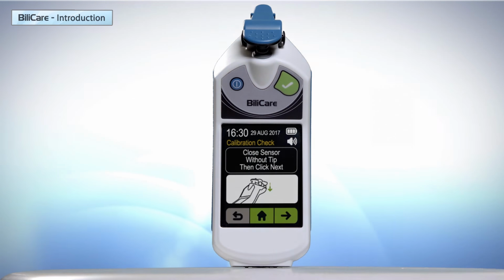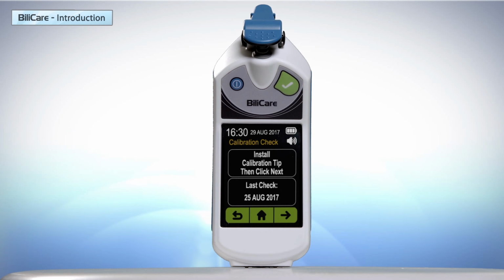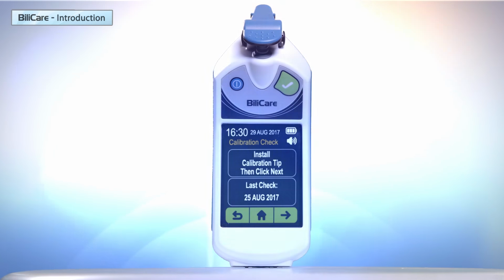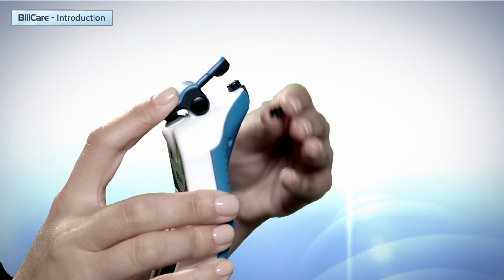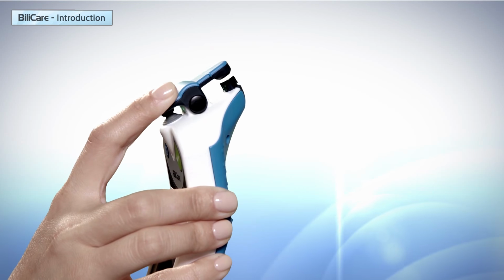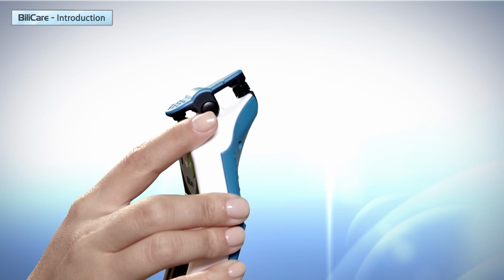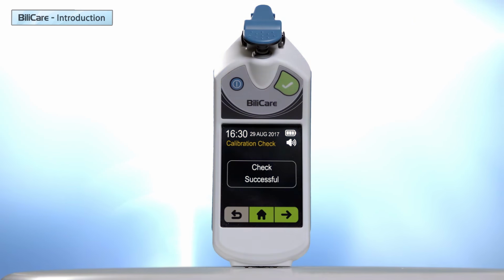Click Next. The next screen asks the user to place the calibration check tip. Place the tip on the sensor and click Next. If BiliCare works properly, the check successful screen is displayed. If the check failed, the check unsuccessful screen is displayed, and the device should be sent to service.